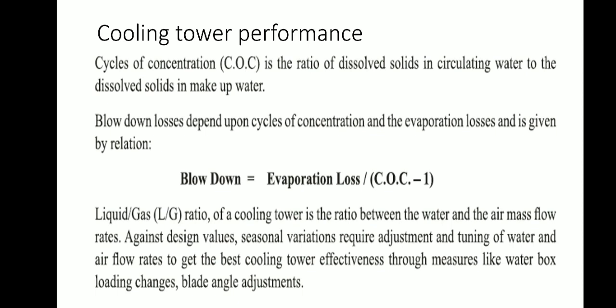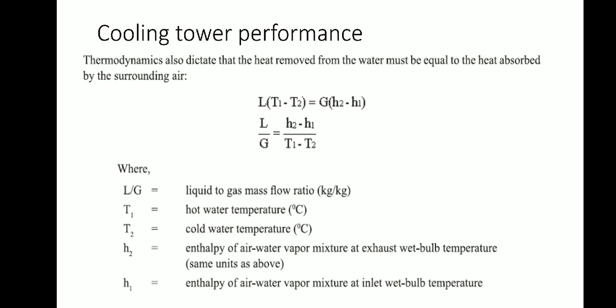Then liquid gas ratio is a very important parameter while computing the cooling tower performance. The L/G ratio of a cooling tower is the ratio between the water and airflow rates. Thermodynamically, the energy balance between them, cooling tower and gas, is L into T1 minus T2 equals G into H2 minus H1. L is the liquid, which is hot water from the exchanger, and G is the airflow rate. T1 and T2 are the hot water inlet and cooling water exit temperatures, and H2 minus H1 is the enthalpy of air at inlet and exit.